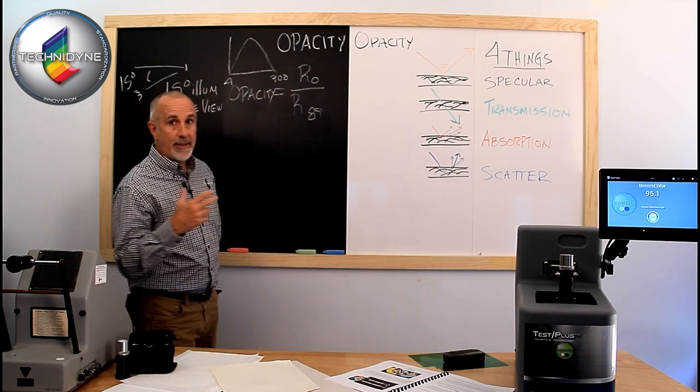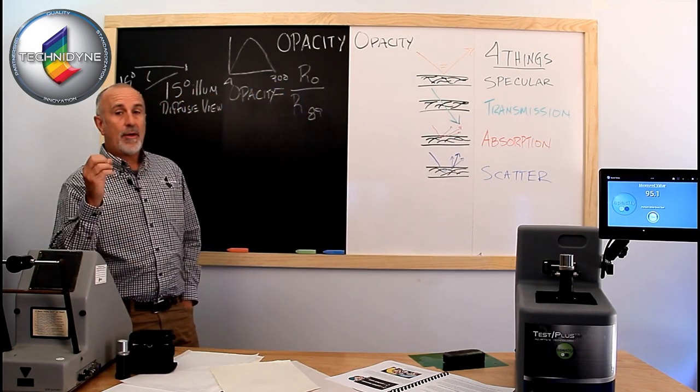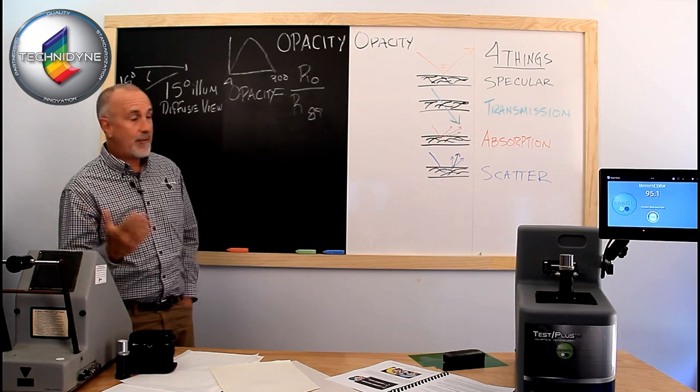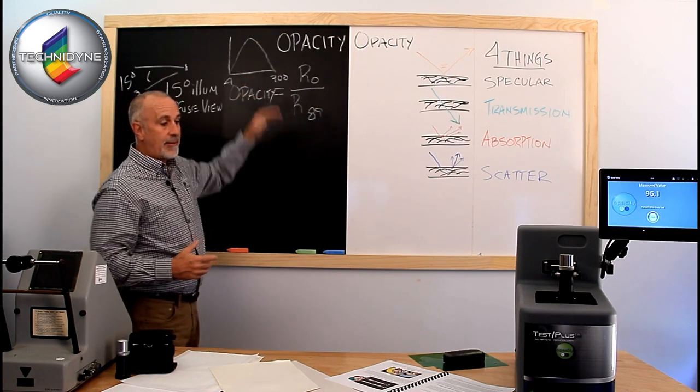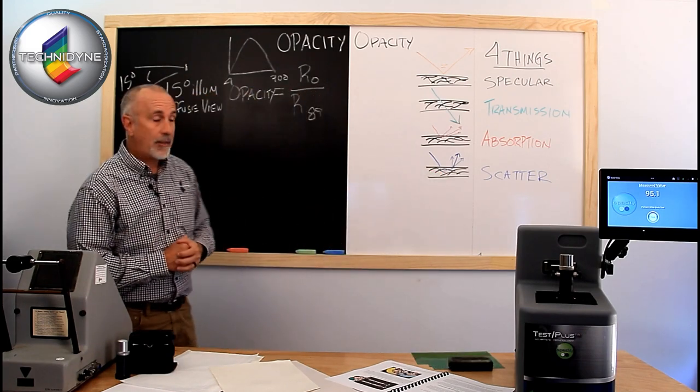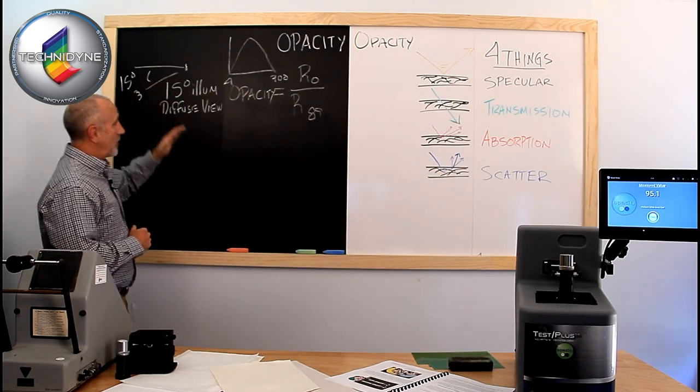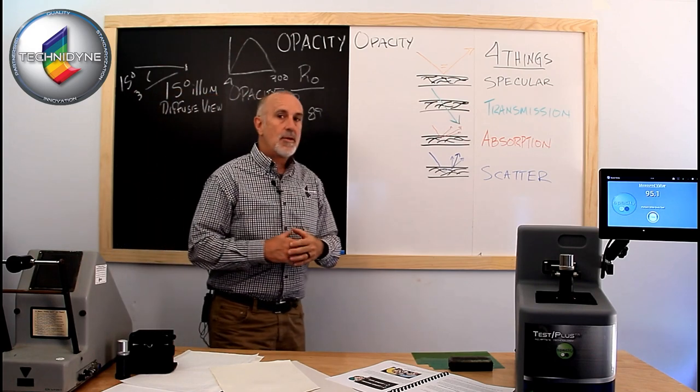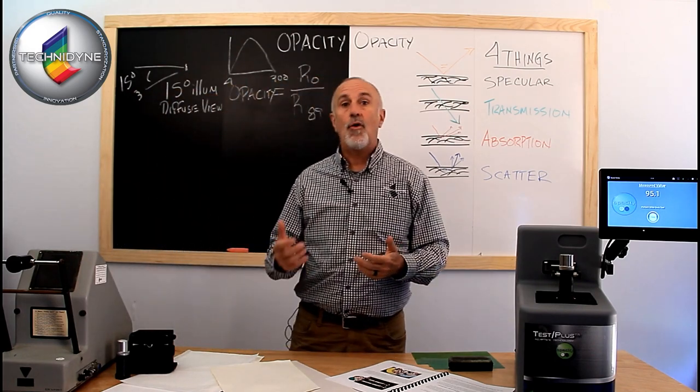So you've got that backing. We're looking at the illuminant A, the Y function, which represents 572 nanometers. So it's measuring out here in this green region of the spectrum. So it's looking at the sample through a green filter, and we already talked about the geometry. So that's basically TAPPI opacity.